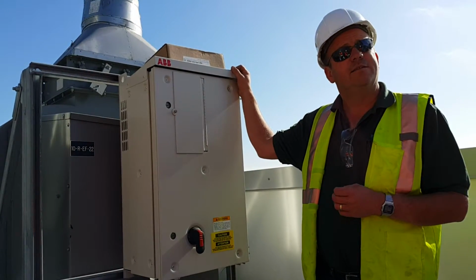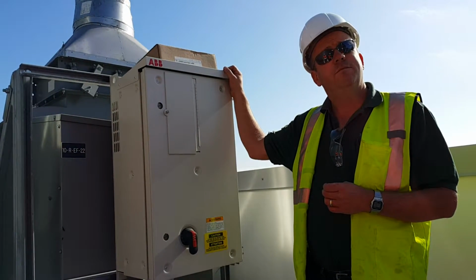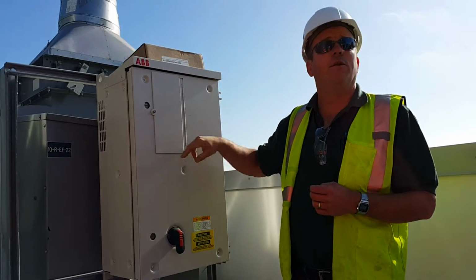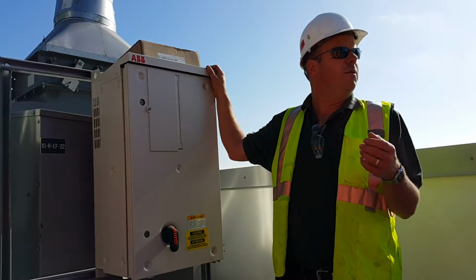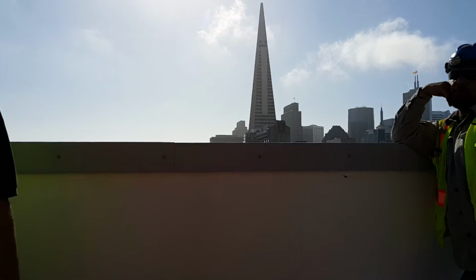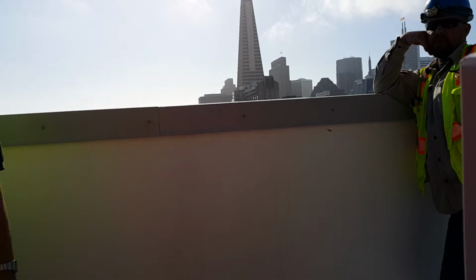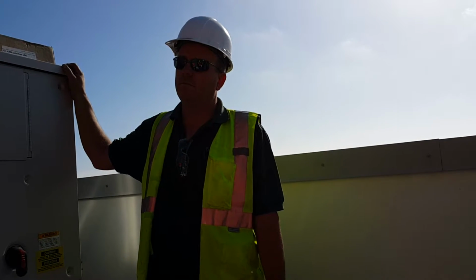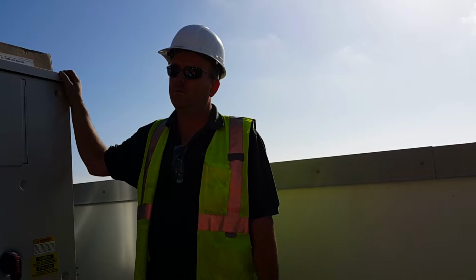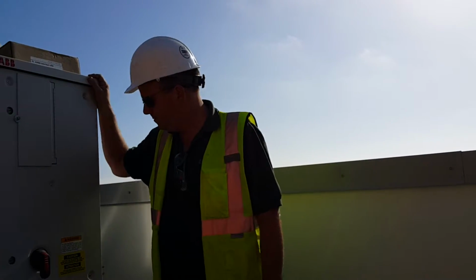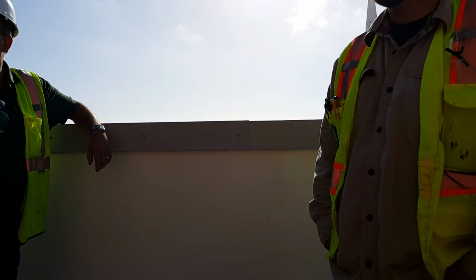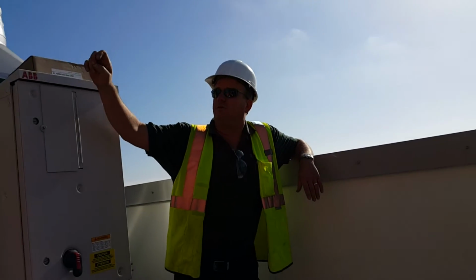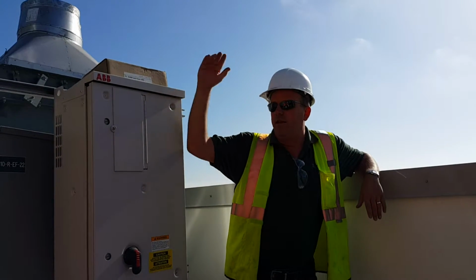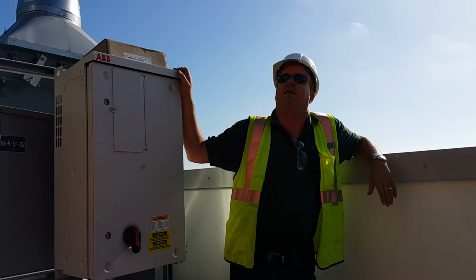And one question. Yes. If we do the fire drill, is it going to affect this? Not this particular one, but some of them will shut down, right? Some of the ones on the floor. These ones are wired, they're interlocked with fire alarm. All the exhaust fans are interlocked. Okay, so I think I know where you're going with the question, but when it goes into alarm and it shuts the VFD down, will it automatically restart? Yes, when the alarm is reset. As long as the fire control panel can close those contacts again, which they usually will, it'll just reset. As long as the BMS system is telling it to start also.